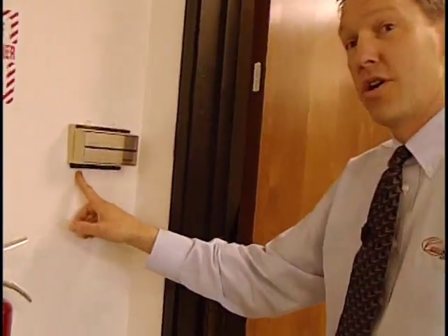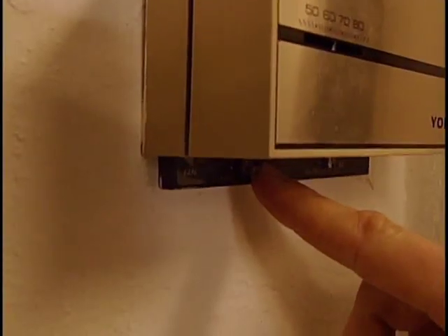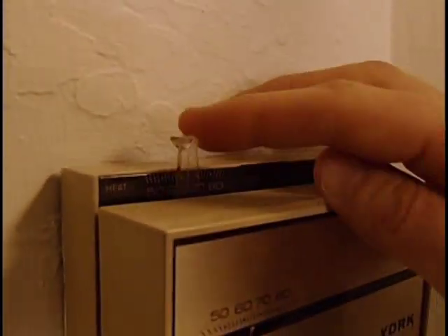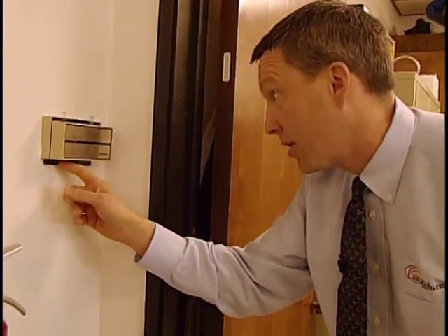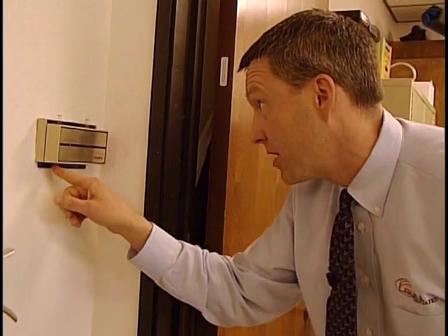You can see the fan mode here. We have the auto mode and the on mode. And over here we have our heating mode and our thermostat controls. The fan is placed into the automatic mode. No fresh air is being supplied to the space when there's no heat or cool cycle demand. So typically we recommend to our building managers to put the thermostat into a lockbox so people cannot tamper with it.